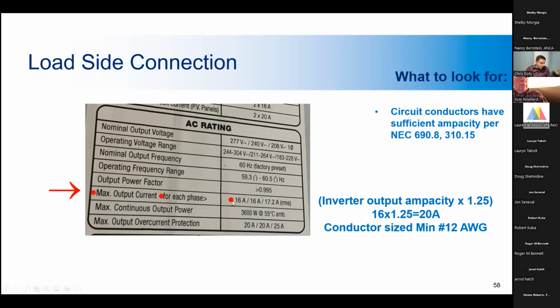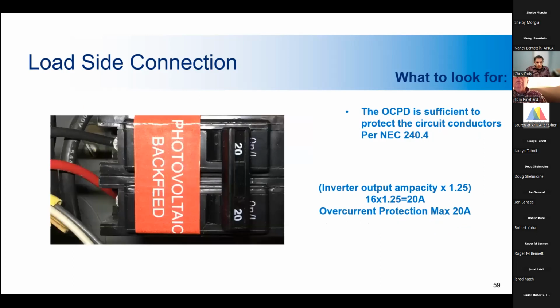So you can see here the max output of this inverter is 16 amps. You would size it to 125% of that, so you get to 20 amps, and that would be a minimum of 12 gauge wire that can hold that amount of amperage. So the overcurrent protection, you want to make sure that the overcurrent protection device you use, whether it's a breaker or a fuse, is properly sized. That's vital to a safe code compliant system.